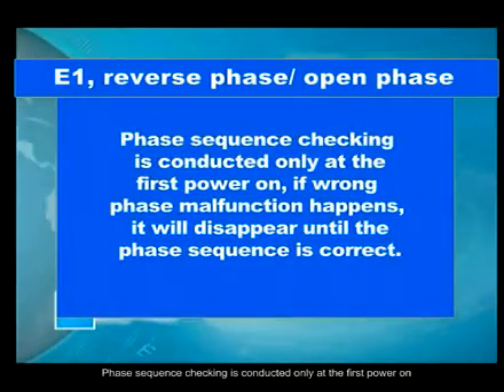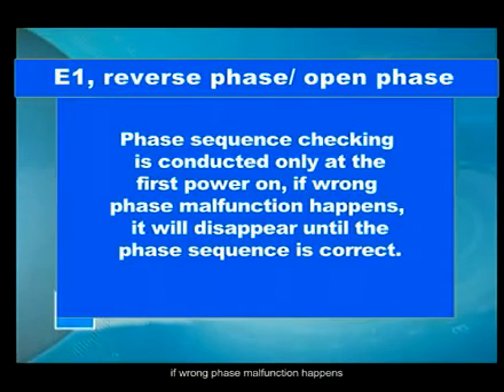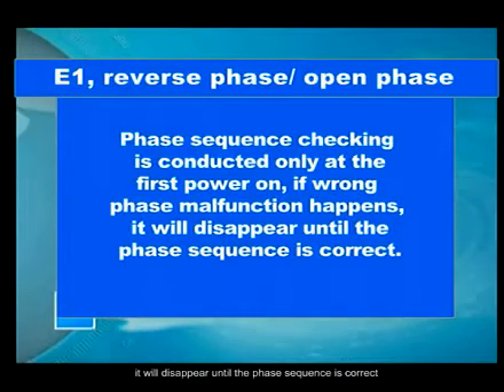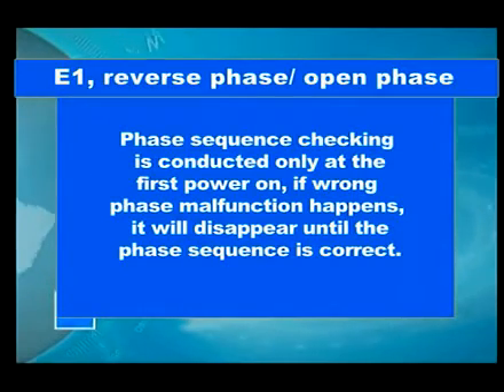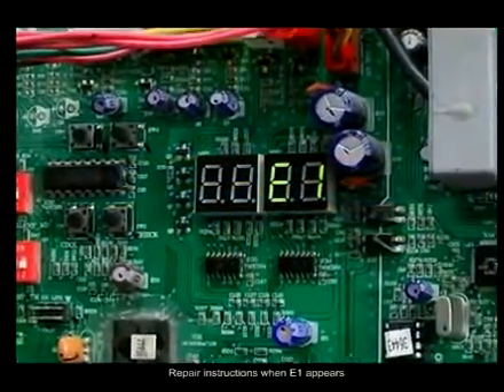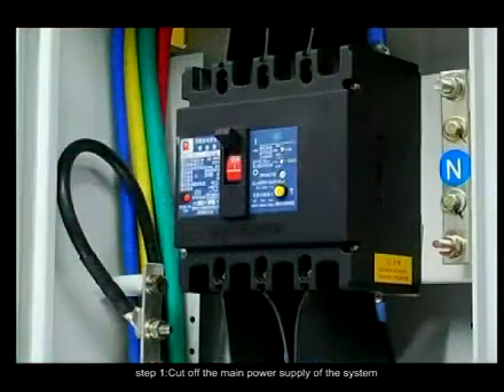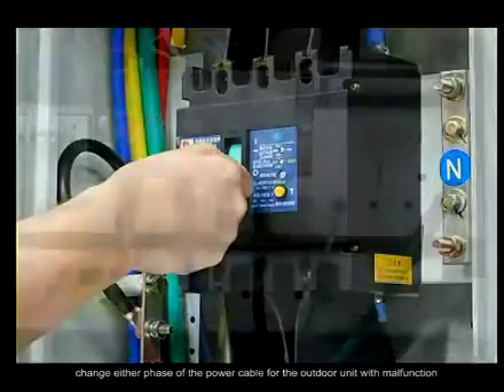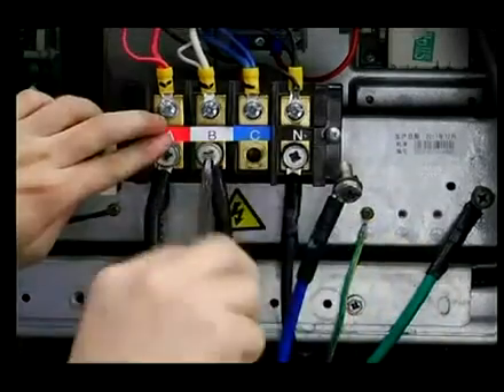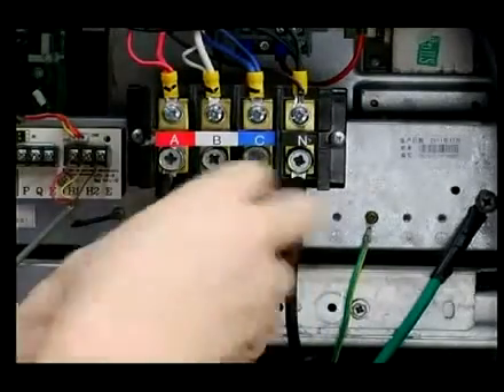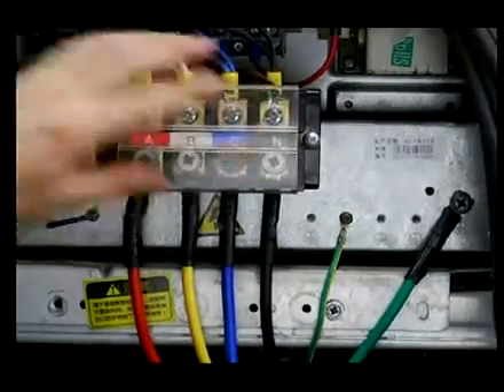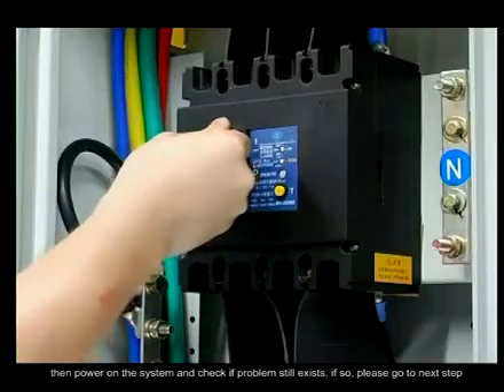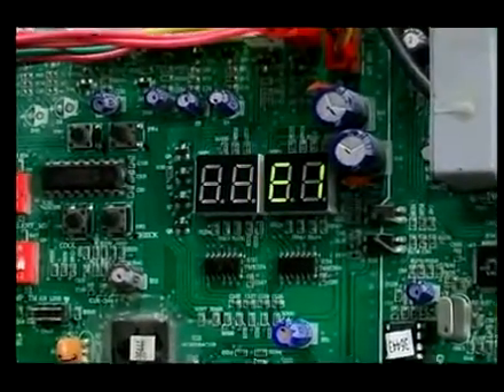Phase sequence checking is conducted only at the first power on. If wrong phase malfunction happens, it will not disappear until the phase sequence is correct. Repair instructions when E1 appears. Step 1. Cut off the main power supply of the system. Change either phase of the power cable for the outdoor unit with malfunction. Then power on the system and check if problem still exists. If so, please go to next step.